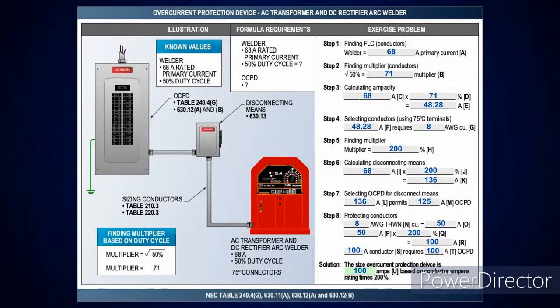I'm going to size the conductor on 75 degrees C terminals. I'll look at table 310.16. The next size above that is 50 amps, which is a number 8. Okay. So now I'm going to look at sizing the overcurrent protection device in 630.12(A). When you go over there, it's going to tell you take a multiplier of 200%. Now, I want everybody to listen to what it says because I've said this over and over. It says each welder shall have overcurrent protection rated or set at not more than. So that means it has to be equal to or it can't be more than.